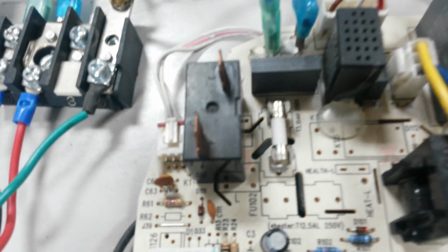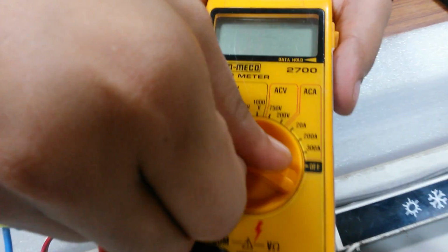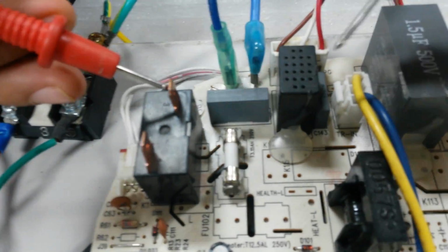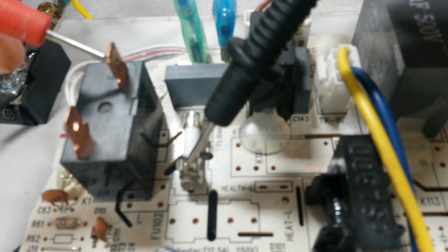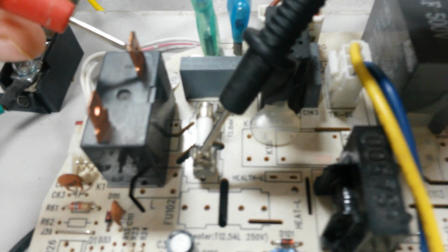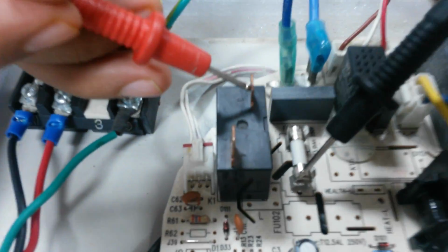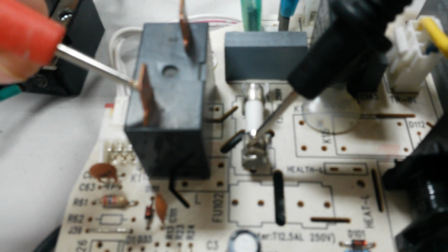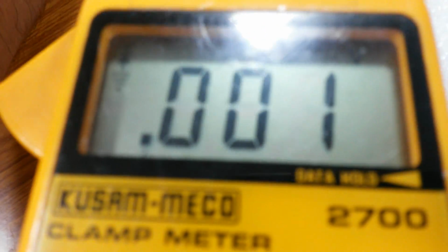How do we come to know where should I put my phase or where should I put my other connection? The best and easiest method for checking the same is by a multimeter. Connect the multimeter in continuity mode. Check for continuity between my relay connections and the fuse. There is no continuity, that means my phase will not be fitting here. If I check on the next component, you can see that there is continuity. Since there is continuity and a beep sound, my phase supply will be given out here.